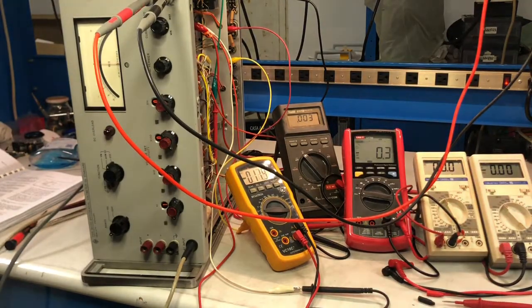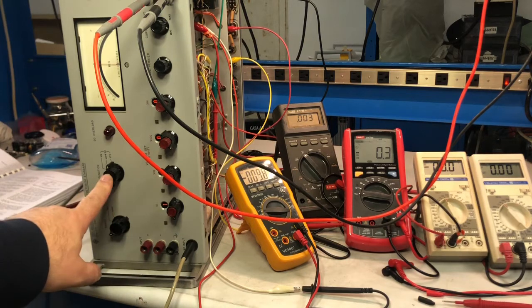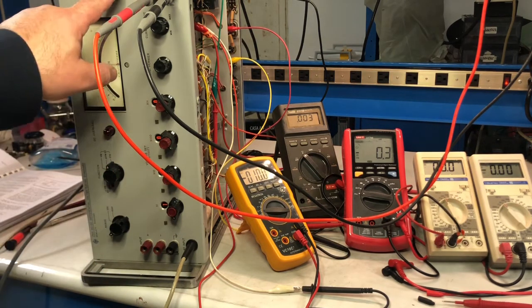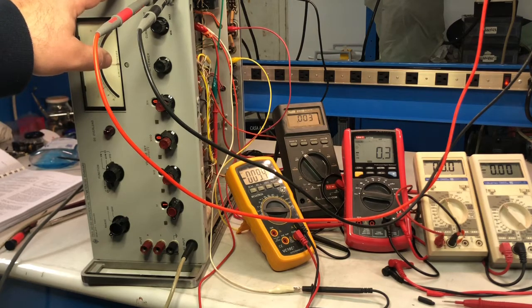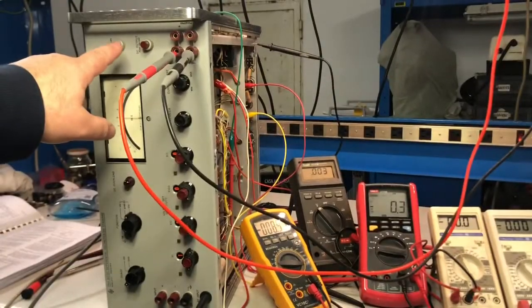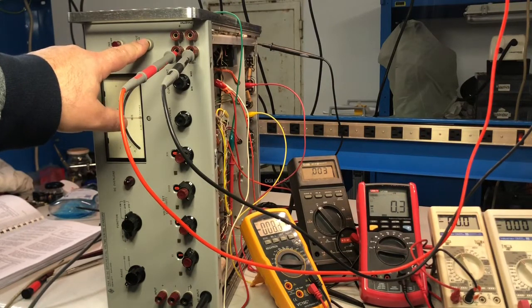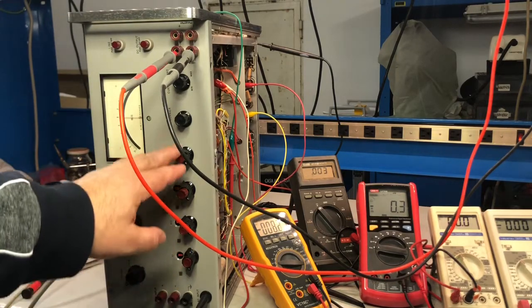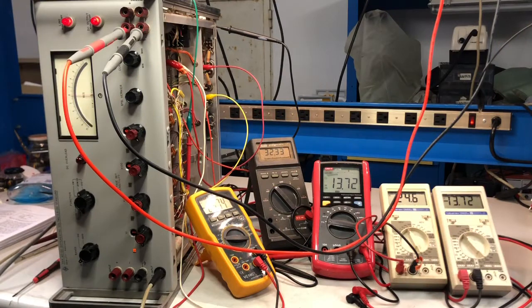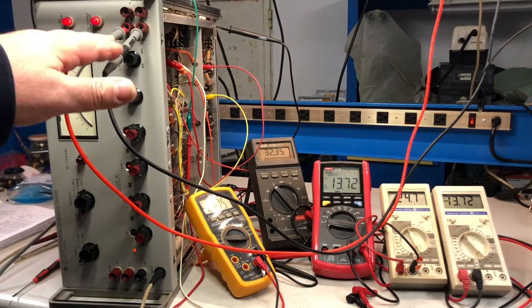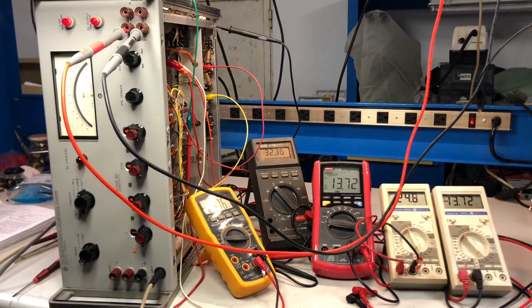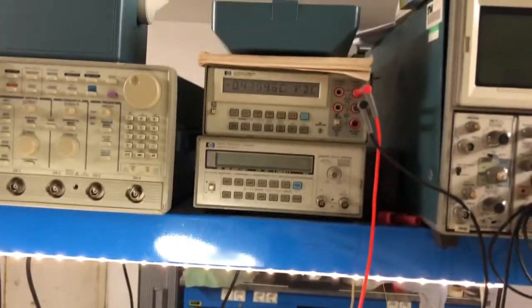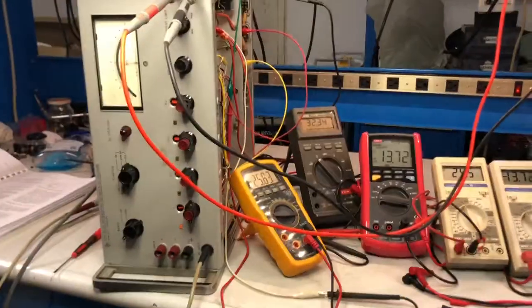I have set the instrument as DC standard, and I will power on with this, enable with this, and then read the output. I should have 1 volt regulated. Well, everything is powered up and the output is enabled, but unfortunately I'm not getting any output, and indeed I'm reading minus 0.40 volt. So it's faulty, the DC standard.